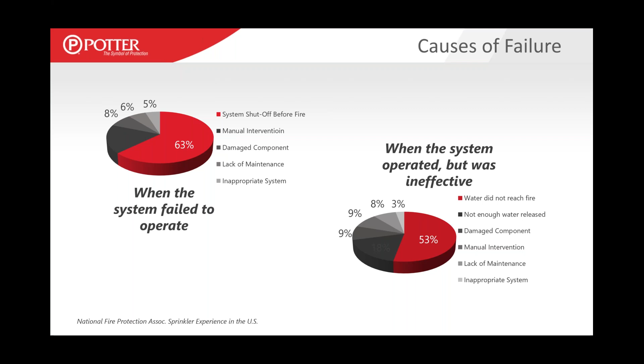So if you take that failure rate data from the earlier slide in, say, a storage occupancy, you know that failures of systems in storage occupancies occur at a higher rate than they do in others. And then you combine it with these failure numbers of why water doesn't reach the fire. So what would cause water not to reach the fire in a storage occupancy, for example? We know that we can put those together and create rules around how we can ensure that water can reach a fire in a storage occupancy. That's through verifying that there's not storage too close to sprinklers and so on. So anyway, that's generally where the rules come from, and again, it gets better as we go along, but that's basically where the concepts behind the rules in NFPA 25 come from.